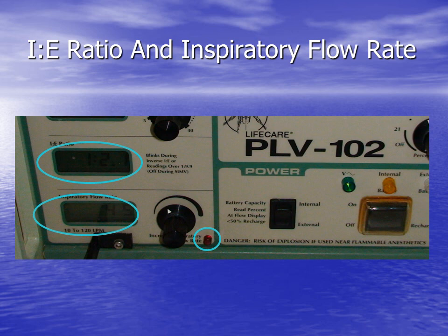If your vent must deliver a higher flow than you have dialed in order to meet your other set parameters, it will deliver this higher flow, but the readout in the inspiratory flow window will flash. The vent also has a red LED which lights up if you need to increase your inspiratory flow or in the event your patient is in inverse ratio ventilation. The I:E readout will also blink during inverse ratio ventilation. In SIMV, the I:E window is blank.